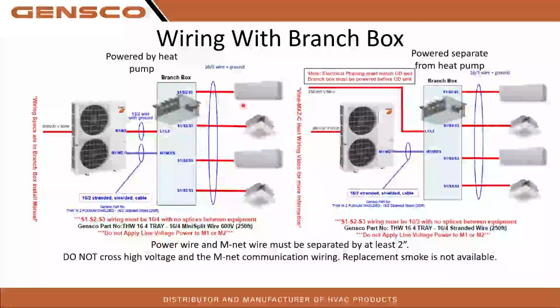Now, once you get over to your indoor equipment, 16/3 wire with ground, or 16/4. It can be solid or stranded. I'd recommend stranded if possible. You're going to have better communication on the stranded, less chance for issues. But Mitsubishi does allow solid core wire on that as well. Some of the older systems had 14/3 listed in the manual. So far, I have not seen any major communication issues from guys using 16/3 and 14/3. I have not had any problems with that.